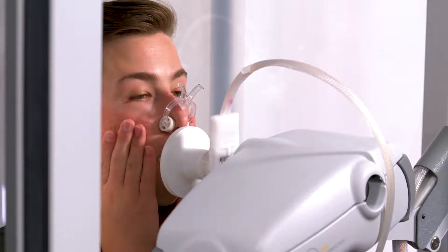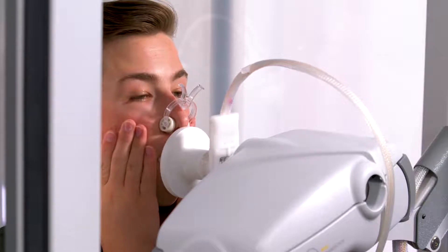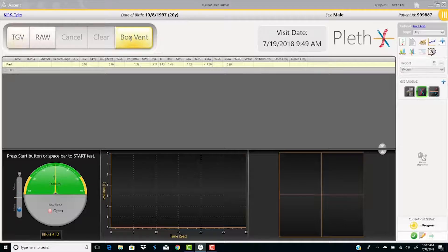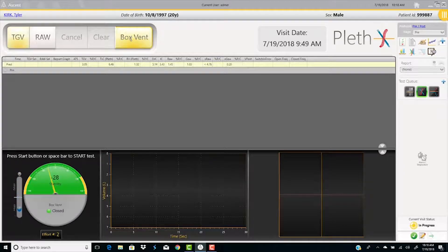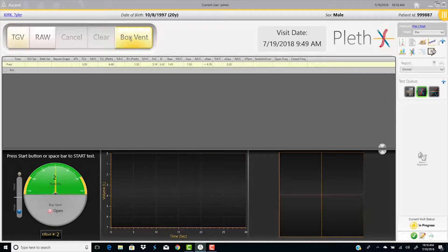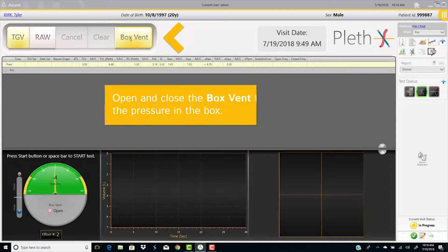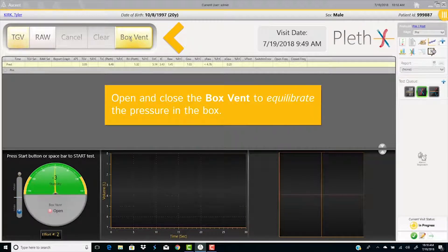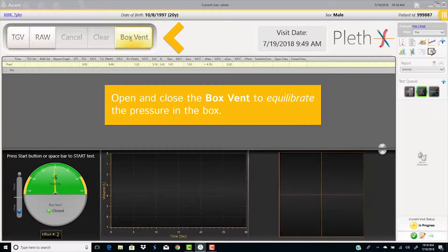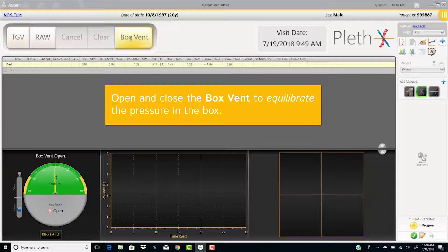Close the door and have the patient breathe normally. Close the box vent. Open and close the box vent, the top left of the screen, to equilibrate the pressure in the box.